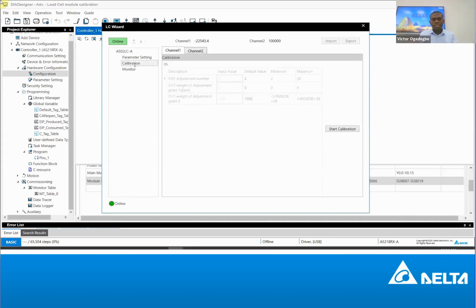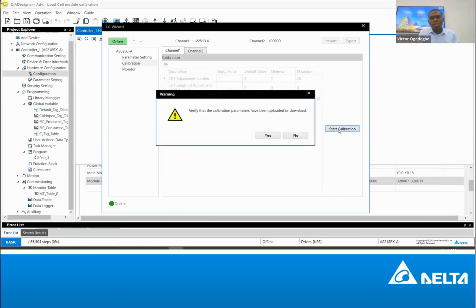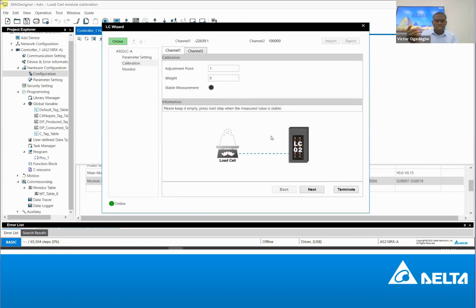And then let's calibrate. So the steps to calibrate are these. I'm online. If you click start calibration, the wizard just takes you through the process. It's quite easy. This is the first step. The minimum number of calibration points is 2. You cannot calibrate with fewer than 2. This is point 1, that is 0. It means there's no load on the sensor as it is now. There's no load. And then let's proceed.